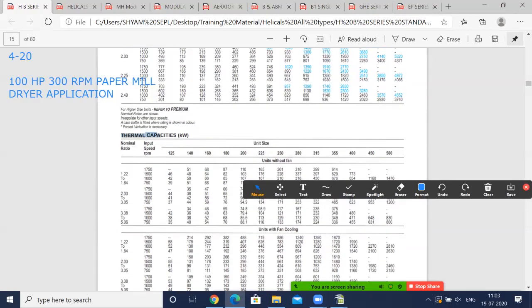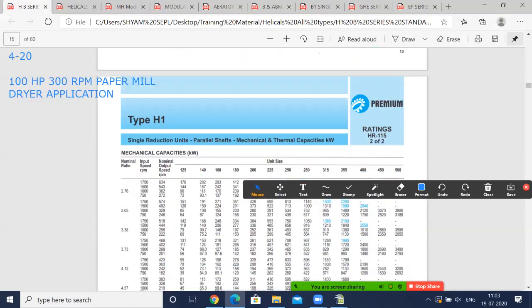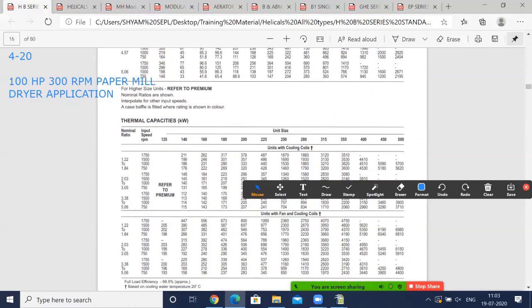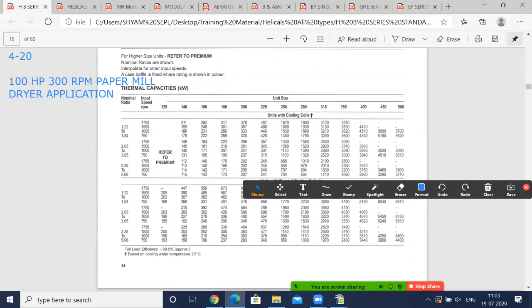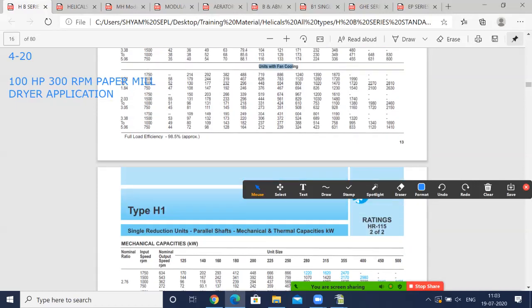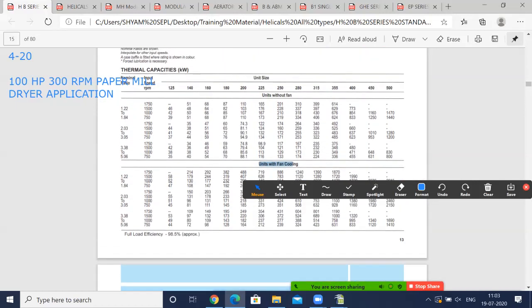The thermal capacities are given without fan, with fan cooling, with cooling coils, or with fan and cooling coils. So there are four stages: one is without fan, one is with fan, one is cooling coil, and one is fan and cooling coil. So the thermal rating also needs to be checked. For ratios between 3.38 and 5 at 1500 RPM, 160 and 180 have a very low thermal rating. It is 49 and 63, while your motor is 75 kilowatt.